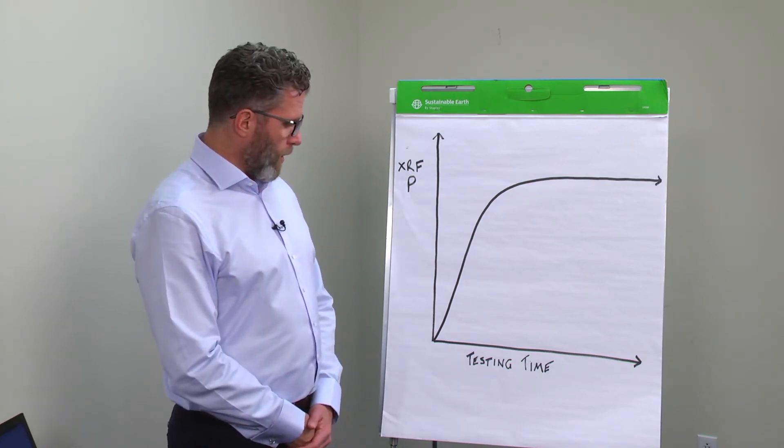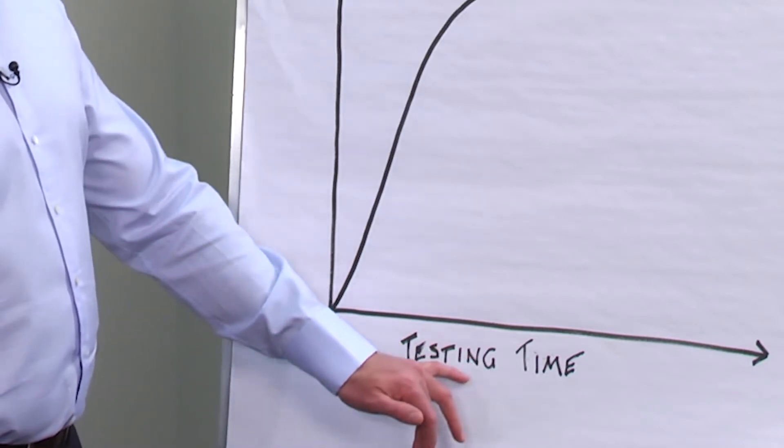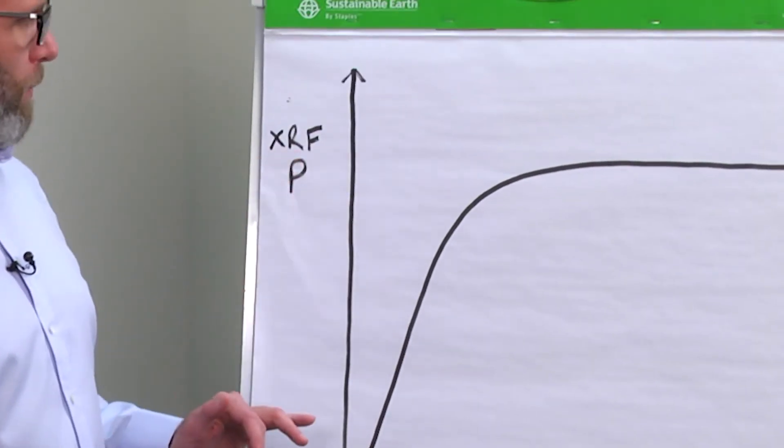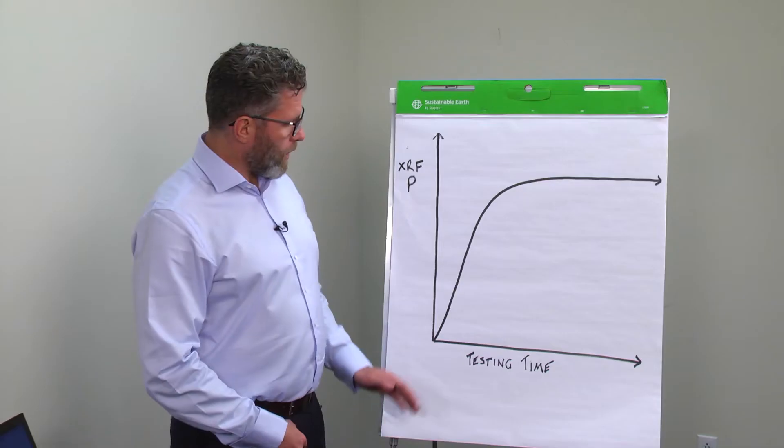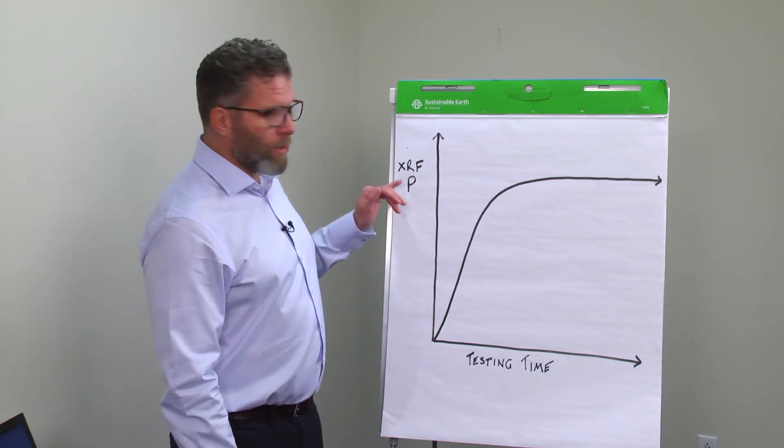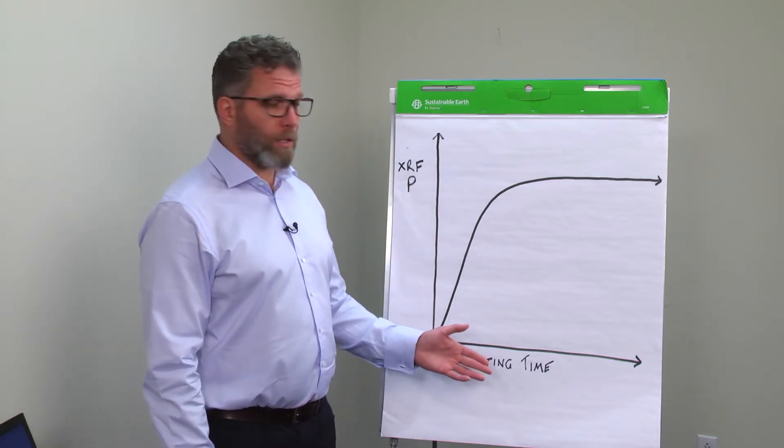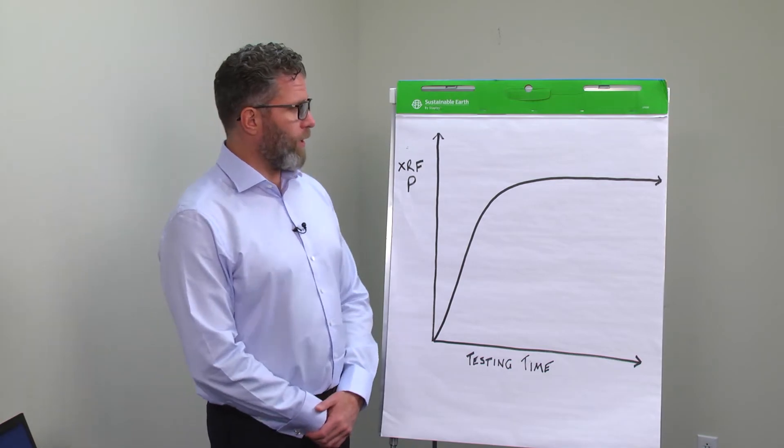is by a simple x-y graph, with x-axis testing time, and y being precision of XRF. Obviously, as you can see here, precision improves over a longer testing time, but the customer actually needs to find their sweet spot.